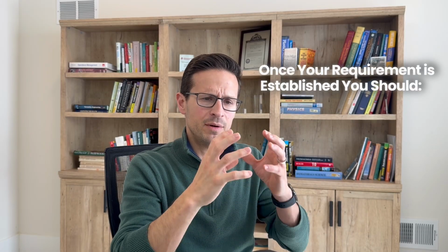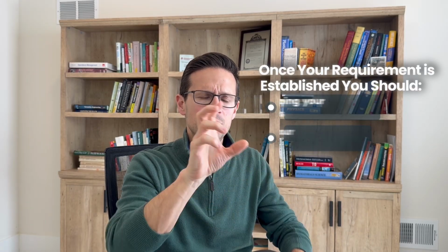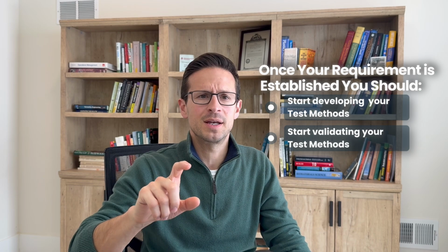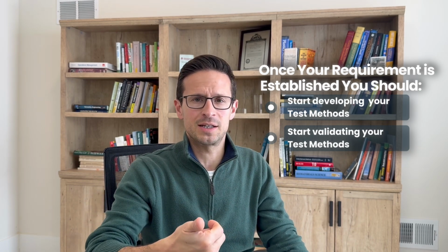So once you have a good idea on which requirements you're going to have, you should start developing your test methods. You should also start validating your test methods. A lot of times it's through gauge R&R studies. Do not leave your test method validation to your design verification stage. You also have to design fixtures and develop test method fixtures.